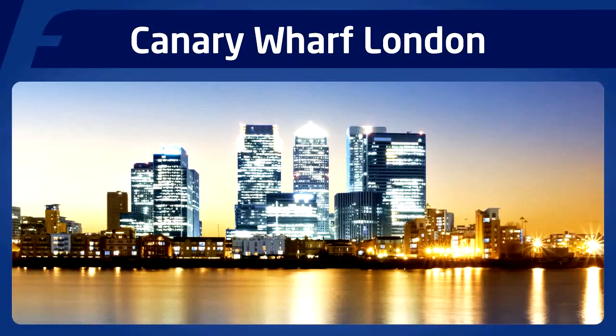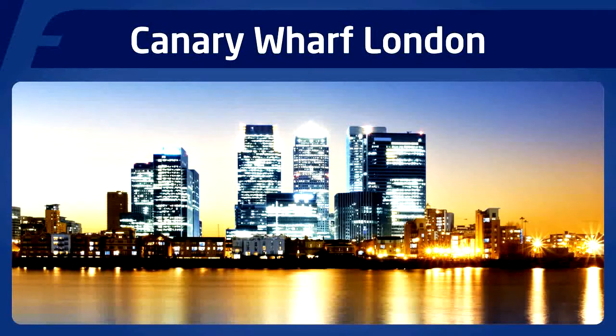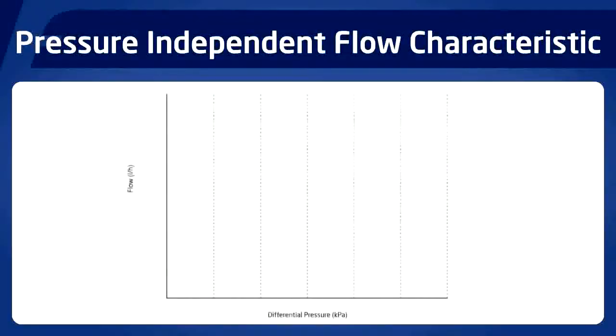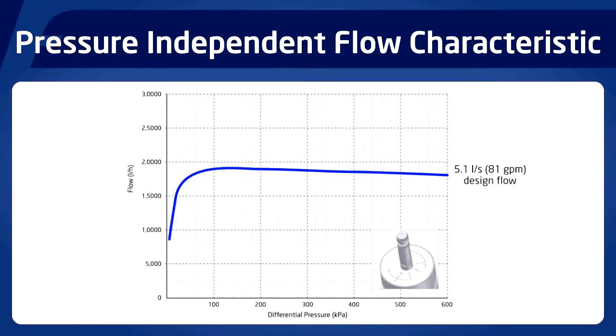We installed the pressure independent control valve in the main tower at Canary Wharf in London and installed a variety of pressure, temperature and flow sensors to be able to record the performance of the valve relative to a conventional two-port valve. The 2.5-inch valve was set for a design flow of 5.1 litres per second.